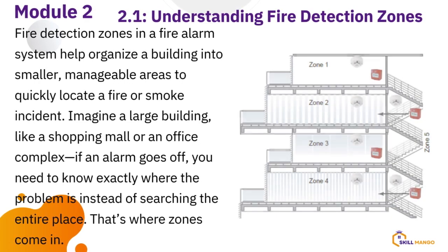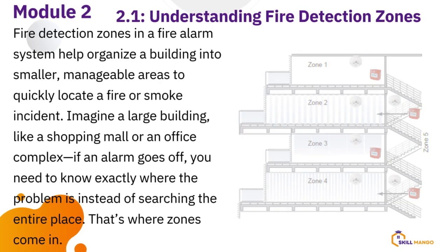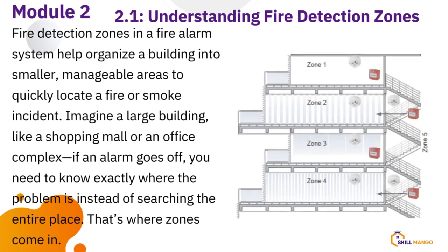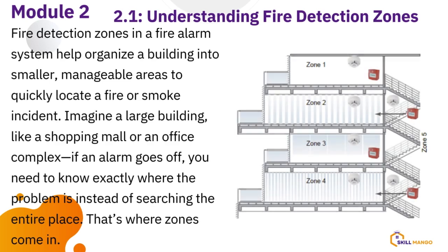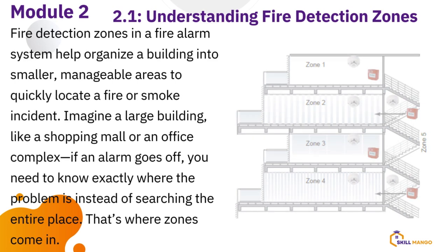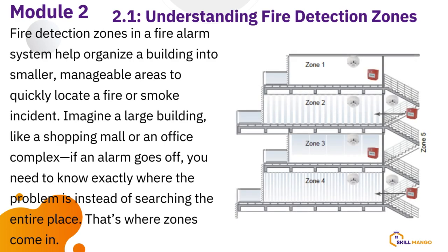All right. I didn't even show this staircase. The staircase has another zone. So all the devices on the staircase belong to one zone. That's five zones. So they are using five zone panels for this kind of installation. Five zone panel. Pardon me for that, I didn't say that clearly. Okay, so five zone panel. All right, so the idea is for you to just zone your areas, so when there's a fire outbreak, you know where it's coming from. That's the idea of zoning.